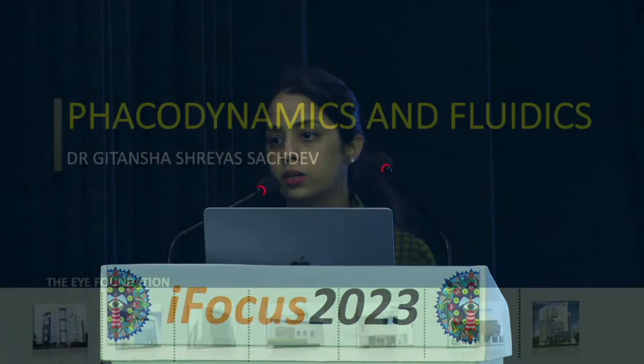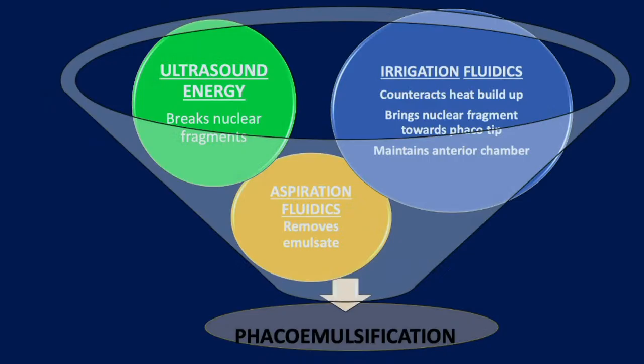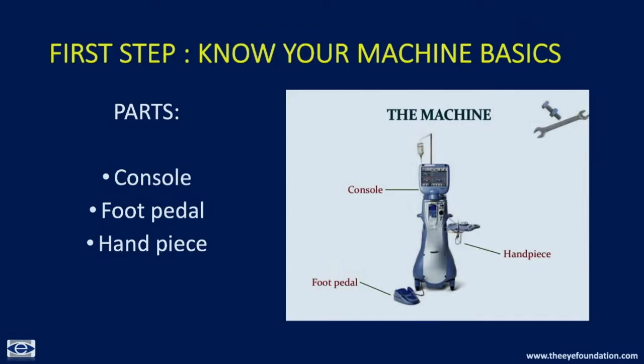The next speaker is Dr. Githansha Sachdev, consultant in cataract and refractive services at The Eye Foundation, with extensive research on phakic IOLs, SMILE, C3R, ICR segments, and femtolaser cataract surgery. She will speak on understanding phacodynamics and fluidics. When doing phaco, three important things come into play: you use ultrasound energy to break down the nucleus, which produces heat, and the irrigation fluidics counteracts this heat buildup, while aspiration removes the emulsified material.